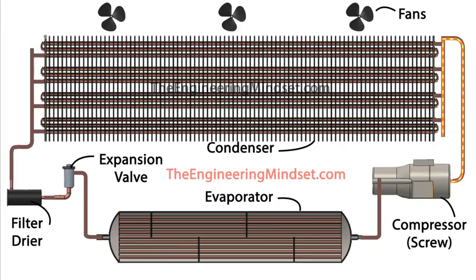So we've got an animated version here, so you can see inside the air-cooled chiller to see what's happening in there. First of all, we've got the compressor, and again, it's a screw type. That doesn't necessarily have to be in every case. Check out our other videos to see about that. So the refrigerant is going to be pushed out by the compressor, and that's going to leave as a high pressure, high temperature, superheated vapor, and that's going to make its way to the headers of the condenser.